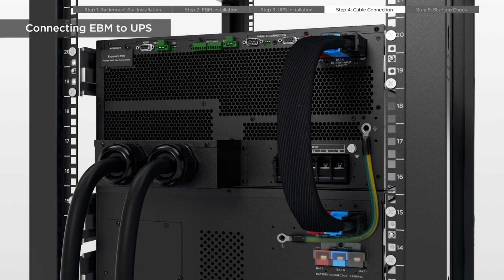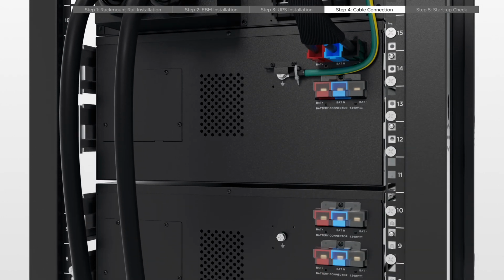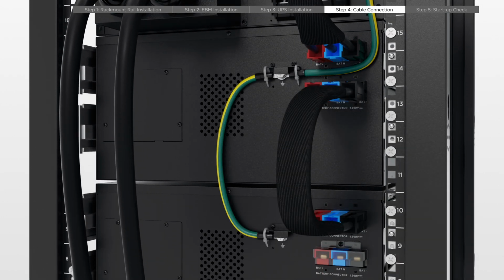Connect the ground wire to the UPS and EBM. Secure the fixed plate to the UPS with 2 black truss screws, fasten with a cable tie, then repeat for the EBM. Repeat the steps to connect the battery cable and ground wire for additional EBMs.